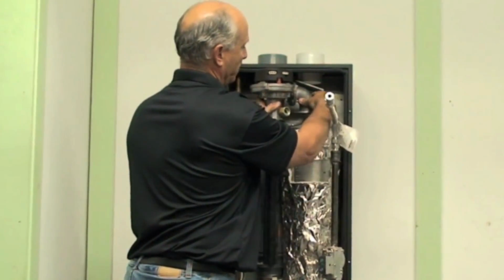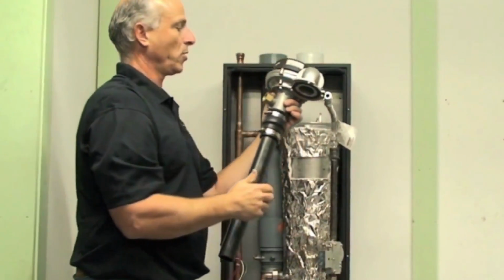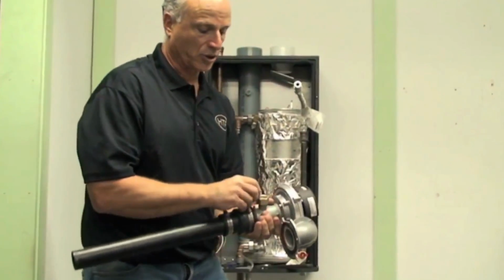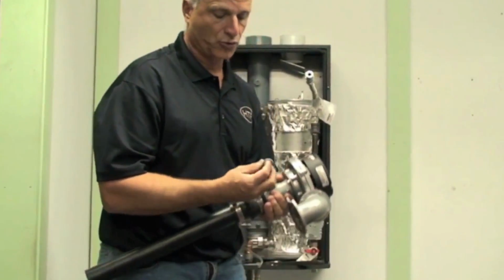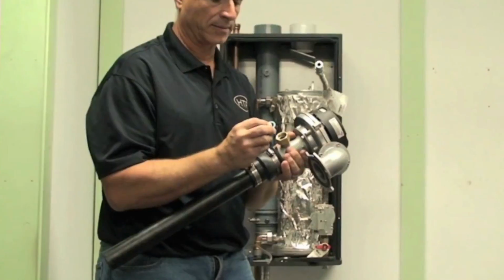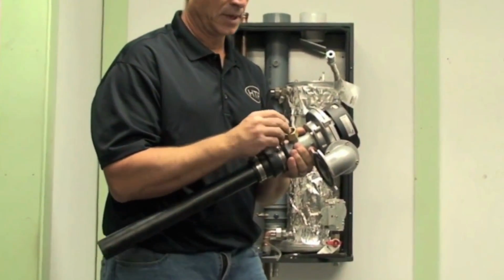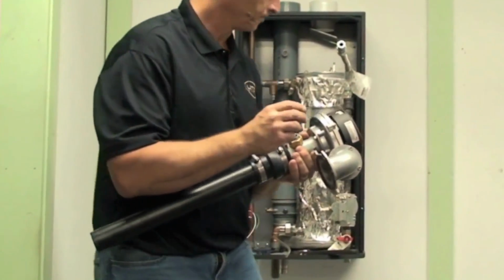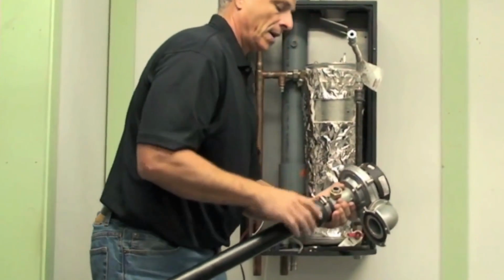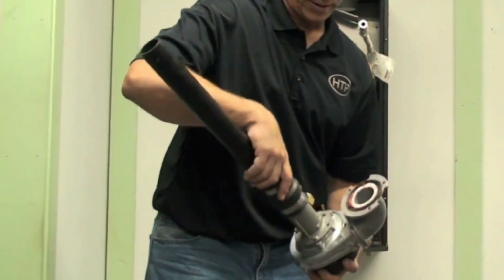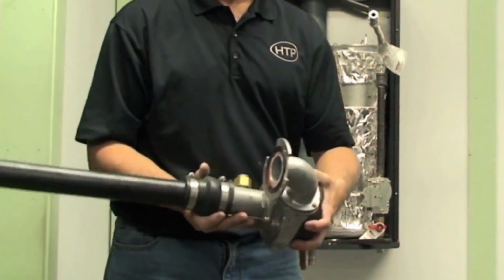Simply take it out, just pull the bulb out. You can see there's an O-ring in here. Make sure that the O-ring goes back in when you go to seal it. This is your gas O-ring. Okay. Then if you need to work on your blower, this is your venturi here.